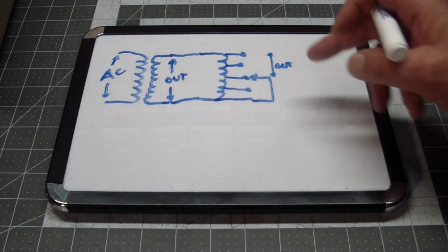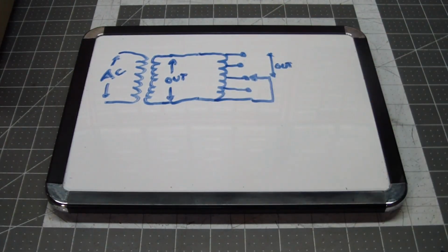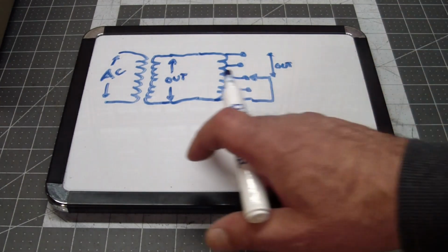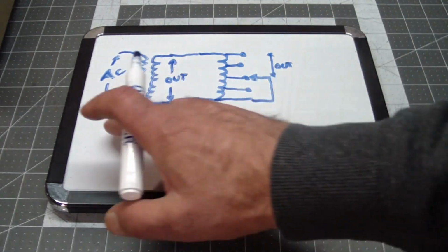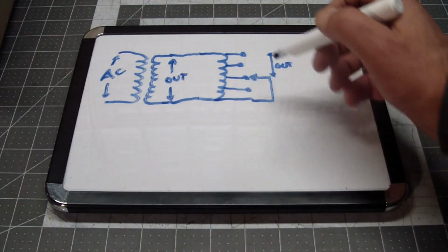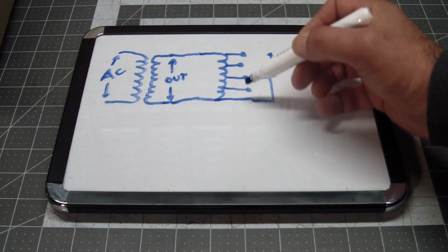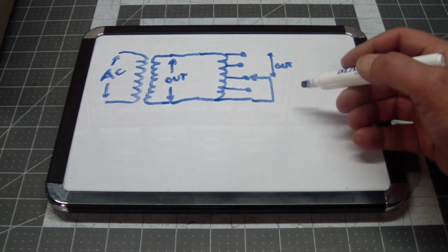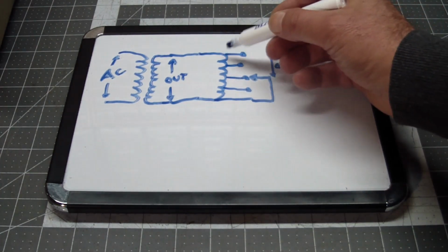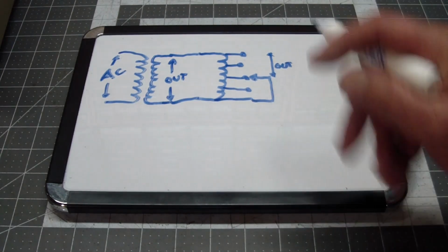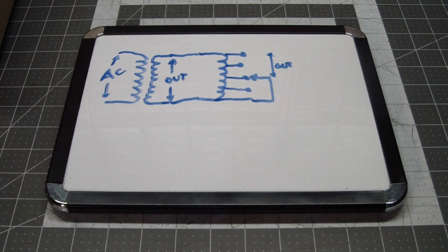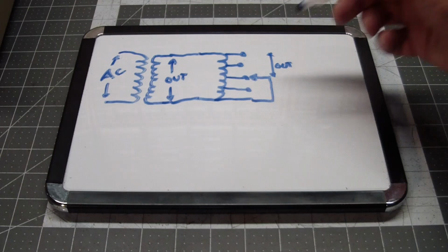This is the same principle used when you buy yourself a voltage converter. You're going, say, from 120 volts to 220, to a country that has 240. What you would do is you got 240 coming in here. Those things don't have isolation transformers on them, so it puts 240 across the top from here to here. But if the tap is right in the middle, then basically we are getting half of the incoming voltage coming out of here. And that's how those little voltage converters make your electrical doodads work when you have an old-fashioned power supply that doesn't self-adjust to different voltages. But yeah, it's the same principle.